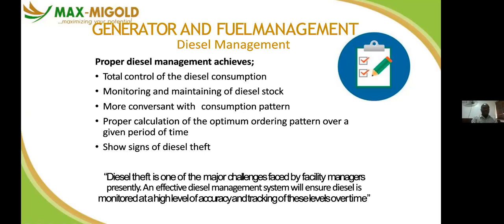So you should know how much your generator consumes every hour at a certain percentage of load. Some people don't know. You that interface with it, you should know. At maybe 25% load of my generator, my diesel should consume this. 50% load should consume this. 75% or 100%, my diesel should consume this. When you start your generator, it doesn't consume the same diesel. It depends on the load your generator is subjected to. So you have to keep track of all these percentage loadings.